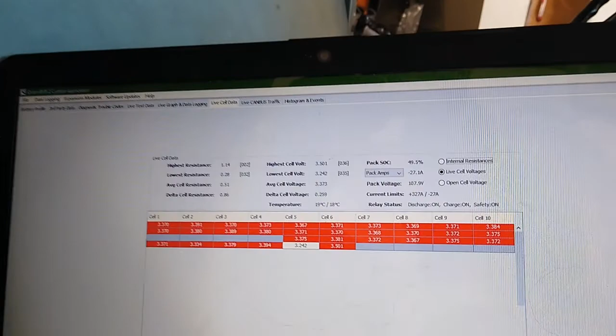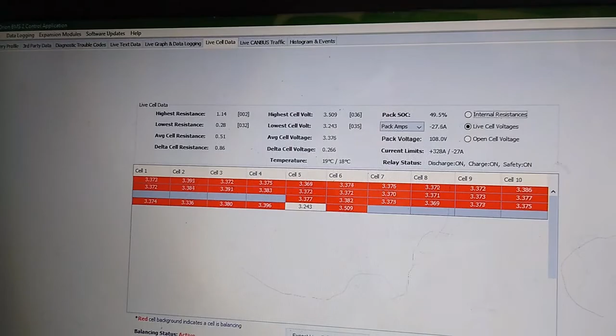Right now it's putting about 29, 27, 28 amps through the pack to recharge it. The battery pack state of charge is about 50%, so 49.5% is where the battery's sitting. We want that to get up to about 95%, and then it'll cut it off, because you never want to overcharge a battery pack.